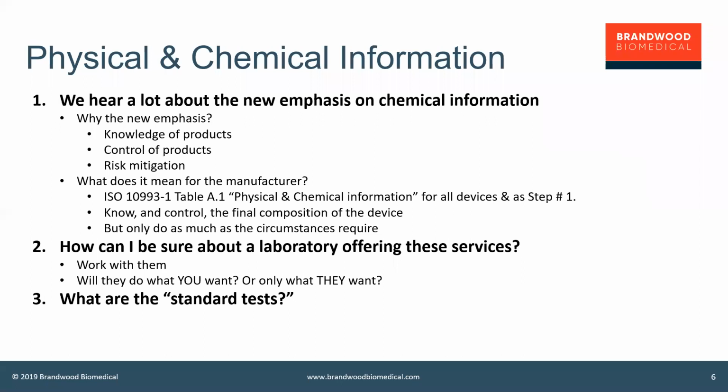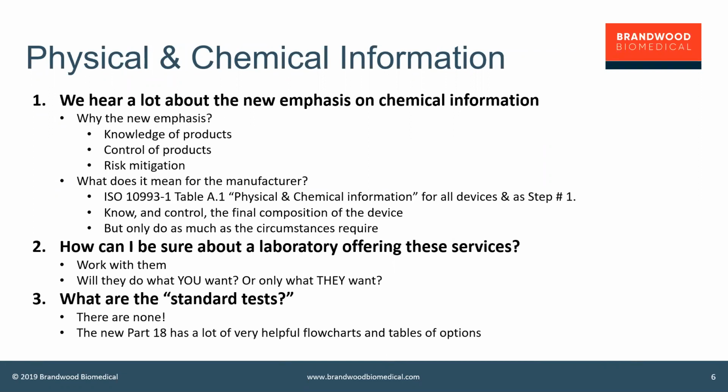Yes, that's right. And one of the questions that's asked is, well, look, what's the standard test that I have to do? Is there just a standard assay or something that I might do? And the bad news is that there are no standard tests, because there is no standard medical device. There are 10 different ways of doing a cytotoxicity test, for example, and you would choose one of those methods according to the type of device that you had. And the same applies when we talk about physical and chemical information.